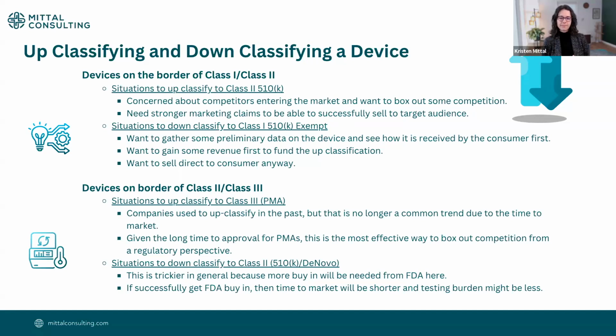Okay, another situation, which is less common than class 1, class 2, but still happens sometimes, is devices that are on the border of class 2 or class 3. So this is where they're really looking at, are we going to be a de novo or are we going to be a PMA? And which pathway should we try to actively pursue with the FDA? This is a more difficult pathway to navigate, and you definitely need buy-in from the FDA, but it is something you should be thinking about really strategically from the beginning and coming to your own conclusion instead of asking the FDA where to fit.